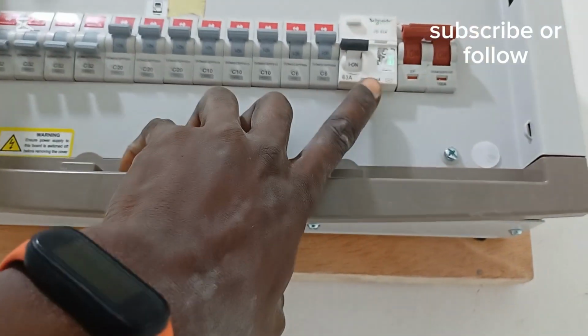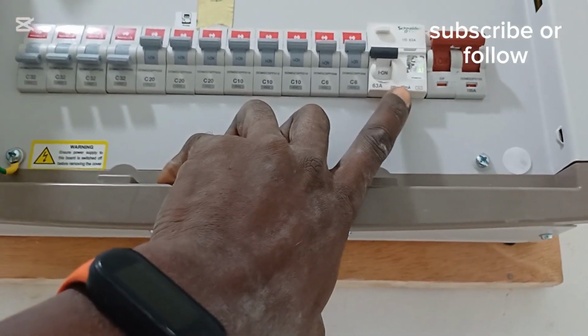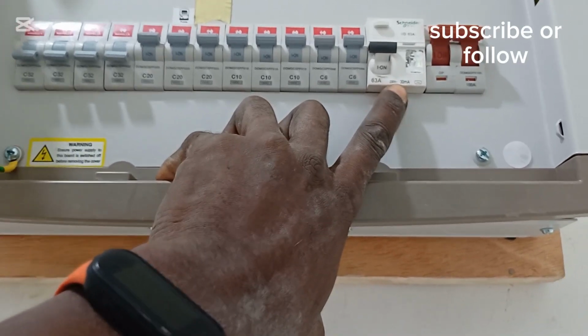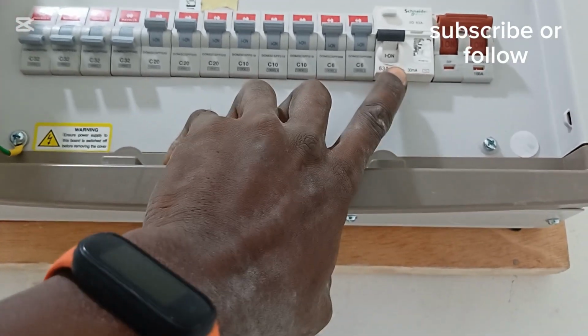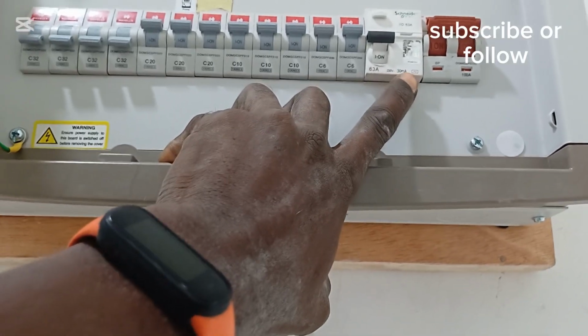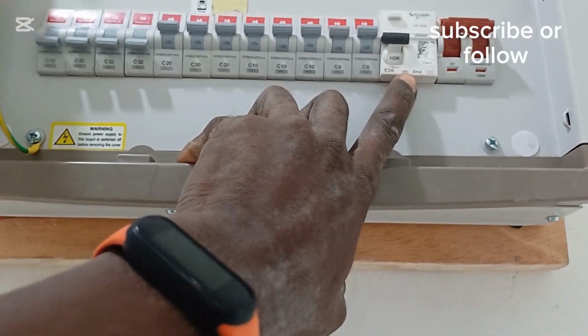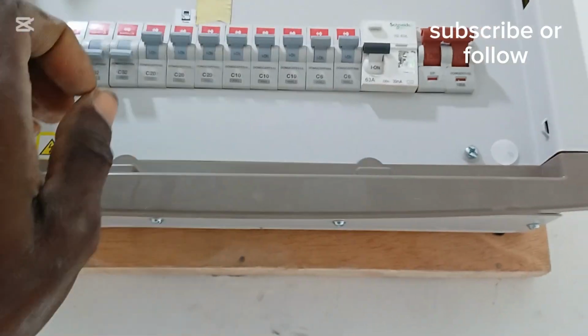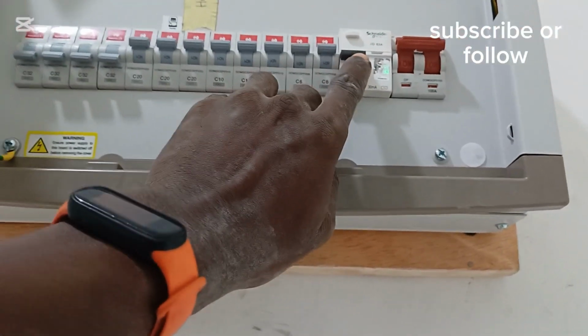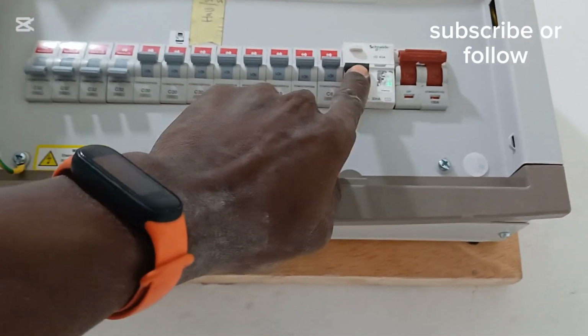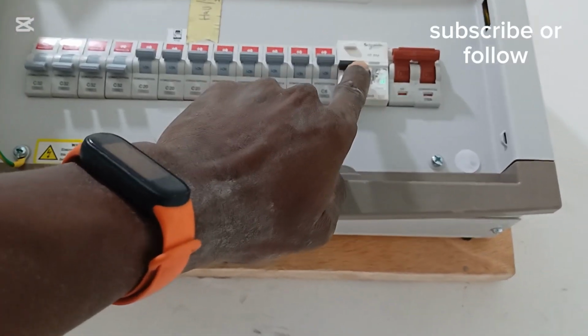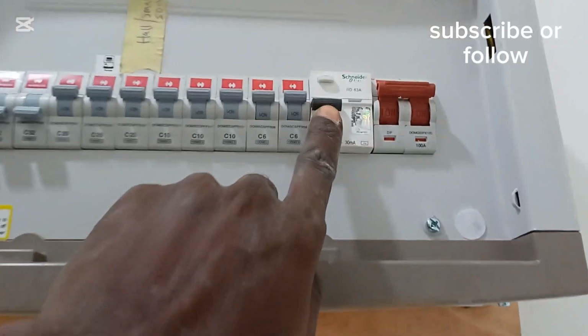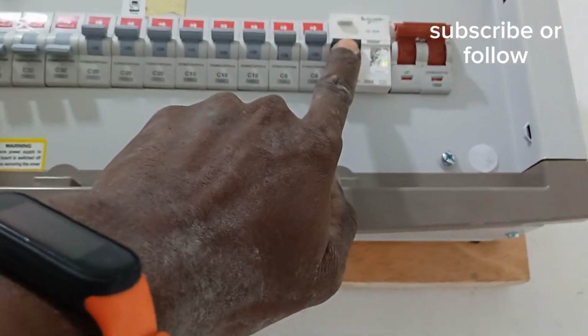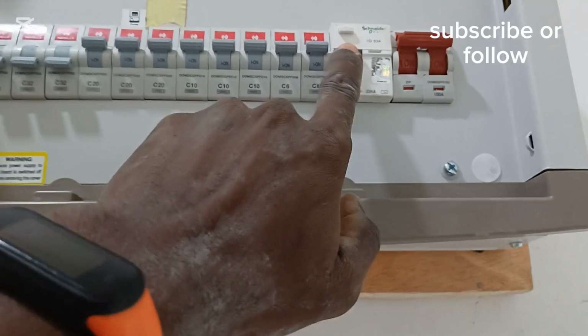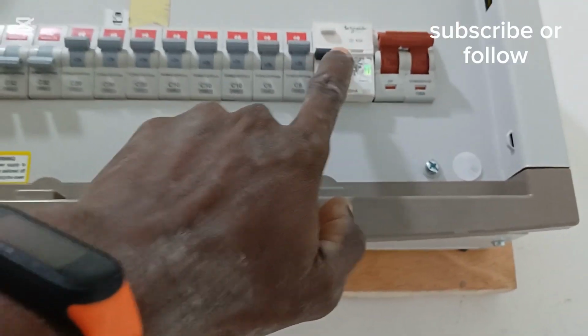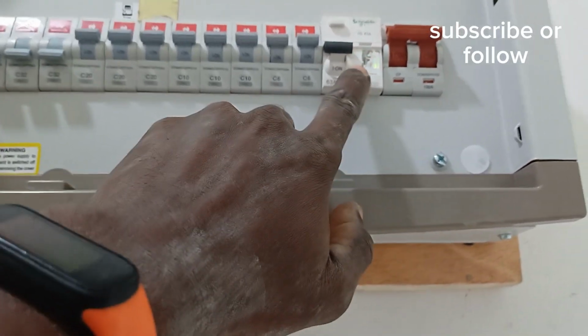But today I've learned something new. The fault was from a neutral and an earth cable. We had earth and neutral conductors coming together, and that was not allowing this to come on. For me, I will call this AI security. With AI security, you can never bribe the person. We were trying all means to pass by, but this wouldn't allow us until we solved the problem.